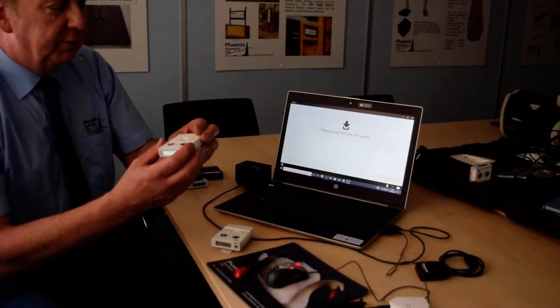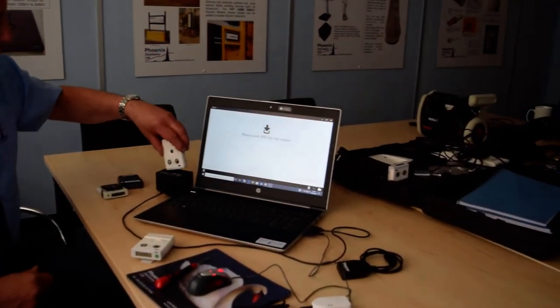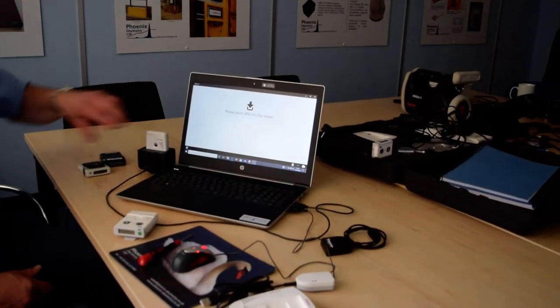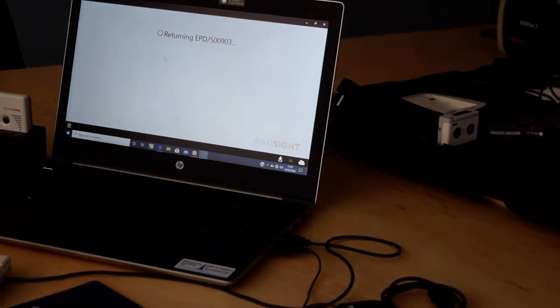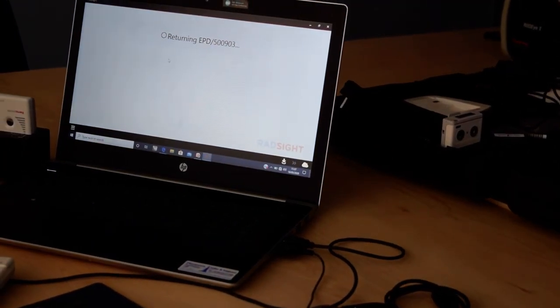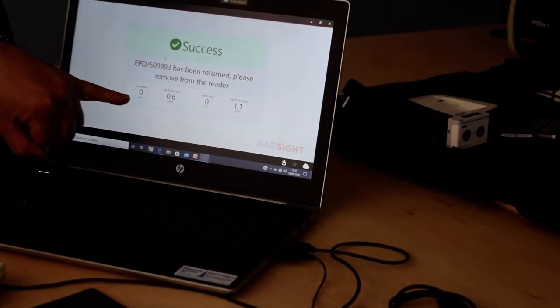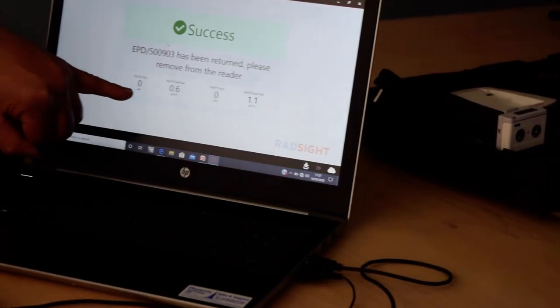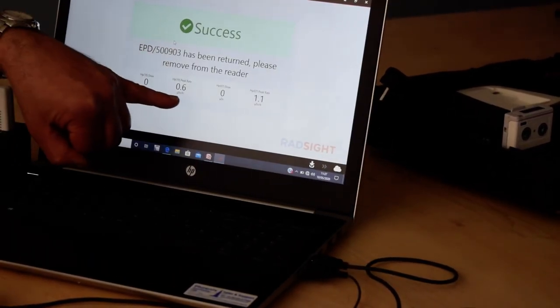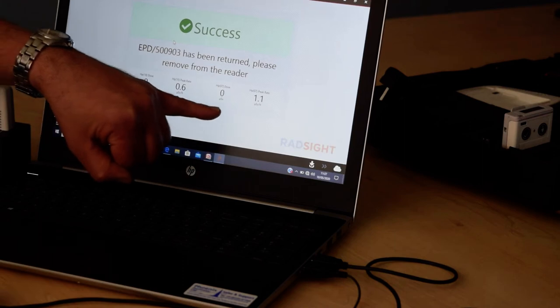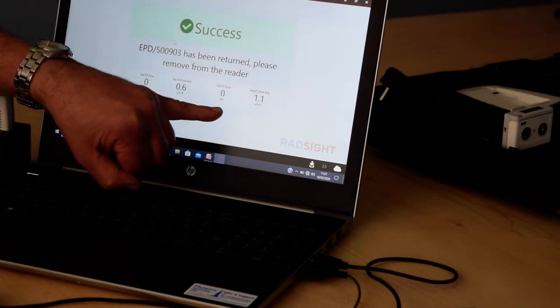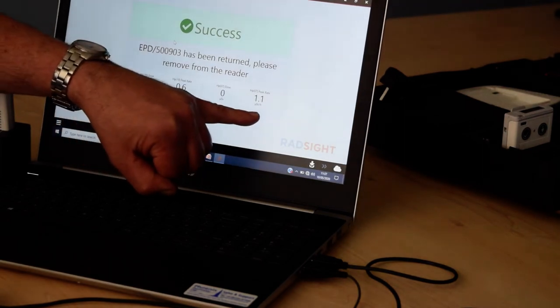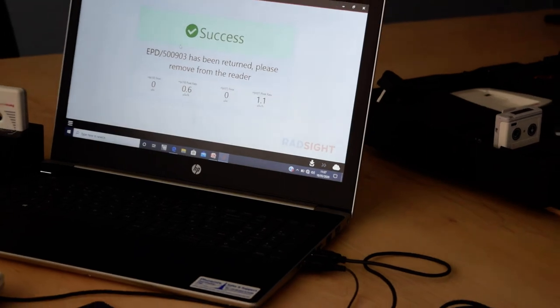If I now return the dosimeter, I simply put it back in the cradle, it reads the dosimeter, and then on the bottom of the screen here, it now shows you the cumulative H star 10 dose, the peak dose rate for H star 10, the cumulative H star 0.07 dose, and the peak H star 0.07 dose rate.